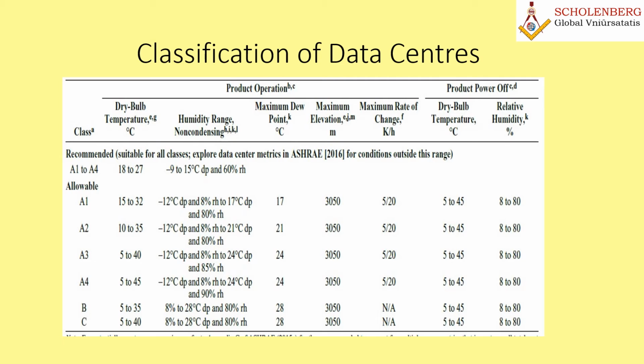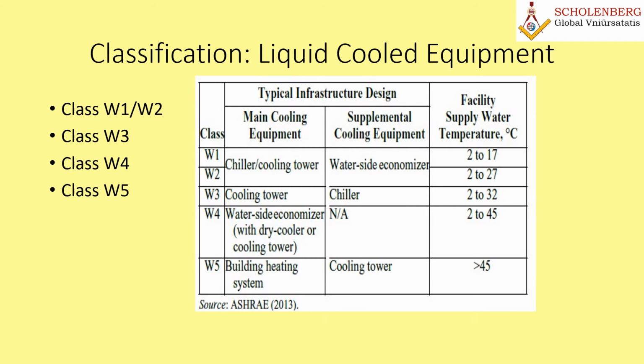They do not have to control or minimize it. A consultant may ask them several questions, like how come 80%, what is the basis of this? No, that is not a problem. You can clearly go with the ASHRAE table and say this is the basis. ASHRAE says the maximum allowable is 60% relative humidity, with a dew point temperature up to 15 degrees Celsius allowed here. So this is what it is. Now let's move to the classification of liquid cooled equipment used for the datacom centers.